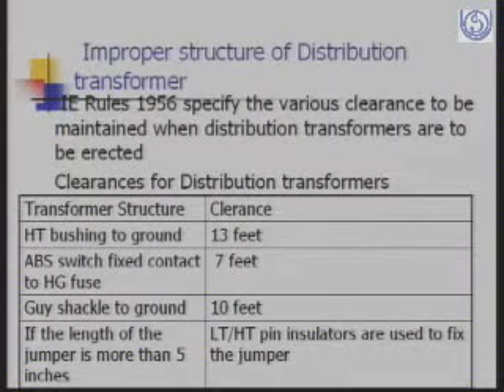failure. Then improper protection. You know, we generally run distribution transformers without protection. In our country, even power transformers are not being protected by circuit breakers, and in distribution transformers, we usually don't provide protection. So if the protection is not there, then we are likely to have distribution transformer failure. We use either overrated fuses or defective fuses. Generally what happens is that people remove the right size of fuse and replace it with a very strong wire or very thick wire so that it never fuses.